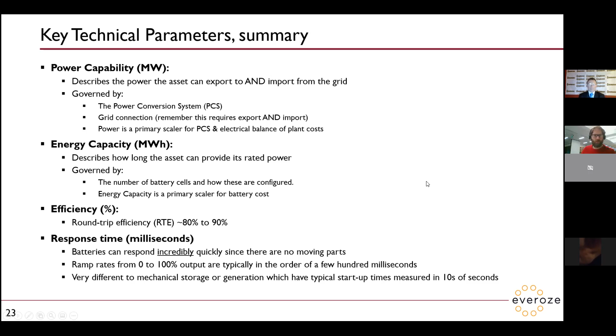You've also got round trip efficiency, as I mentioned earlier, so you lose some energy as heat between importing at your point of connection and exporting again - you've lost a load of energy, fairly obvious. But the key point to a lot of these batteries is the response time, and as I've mentioned before, it's really very fast. That's to date what's set them apart from other sorts of assets, like diesel gensets or what have you.